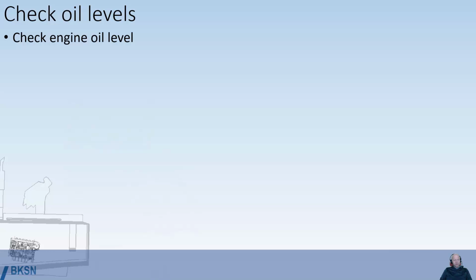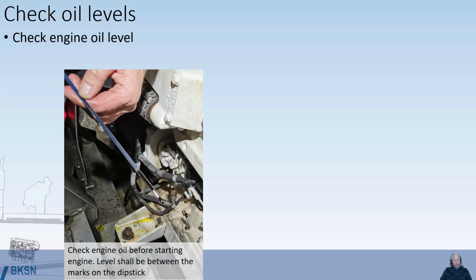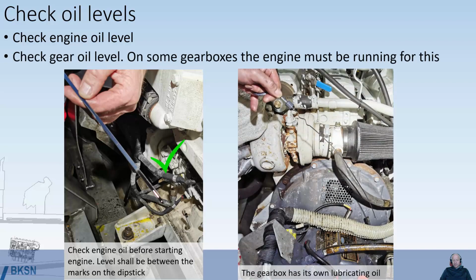Next, you need to check oil levels, engine oil level before you're starting the engine, and the oil level should be between the upper and lower marks on the dipstick. So that's okay. In addition, you check the oil on the gearbox, and it varies a bit whether this should be checked with the engine running or not. So you need to check the manual for your gearbox to find out should the oil level be checked before you start it or after you start the engine. Anyway, the gearbox has its own lubricating oil.